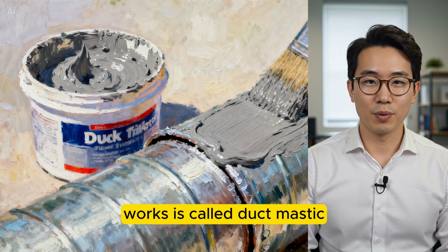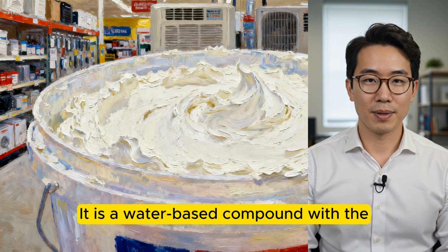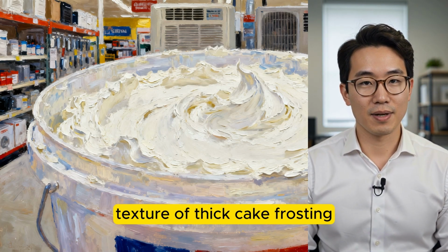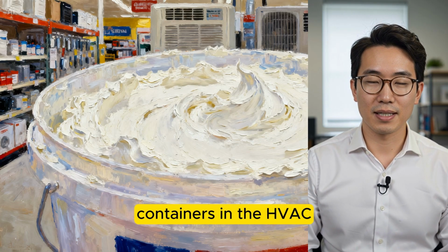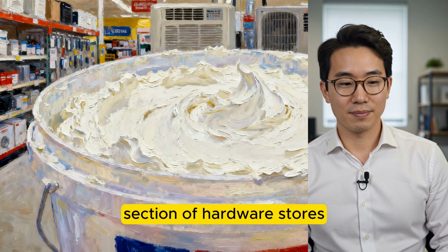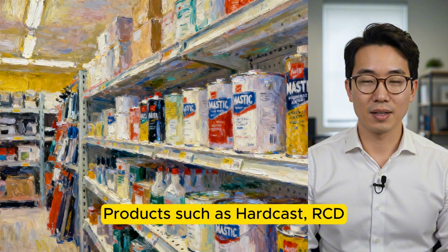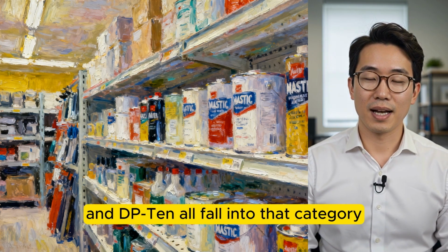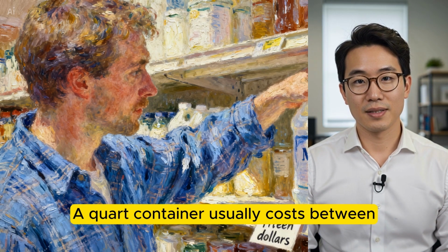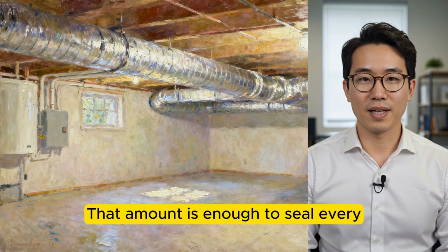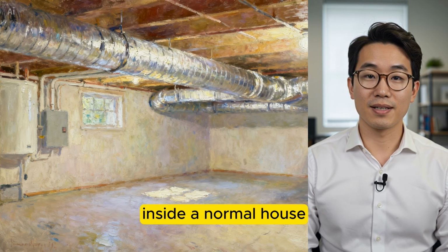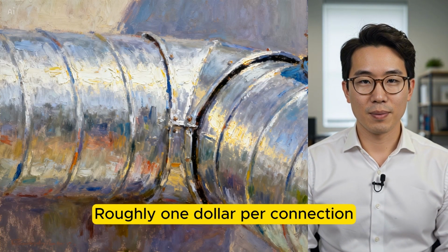The material that actually works is called duct mastic. It is a water-based compound with the texture of thick cake frosting, sold in quart and gallon containers in the HVAC section of hardware stores. Products such as Hardcast, RCD, and DP10 all fall into that category. A quart container usually costs between $12 and $18. That amount is enough to seal every reachable duct joint inside a normal house, roughly $1 per connection.